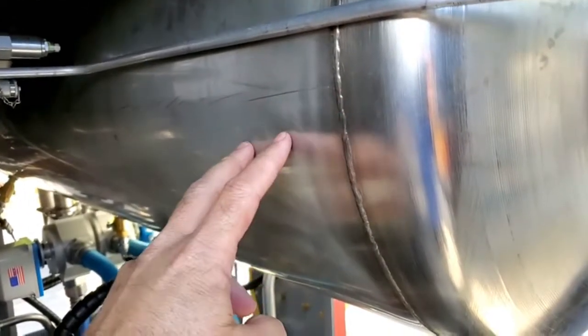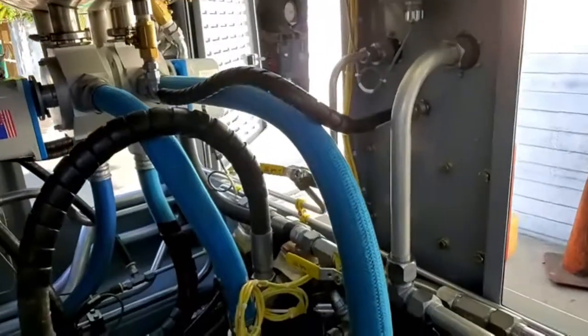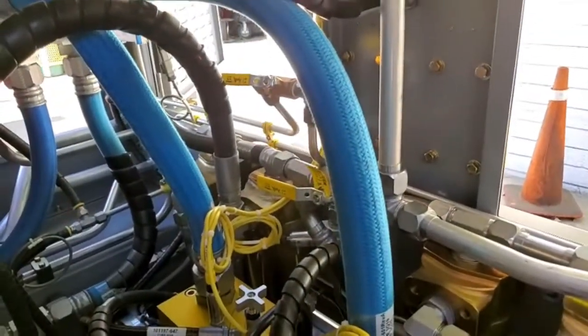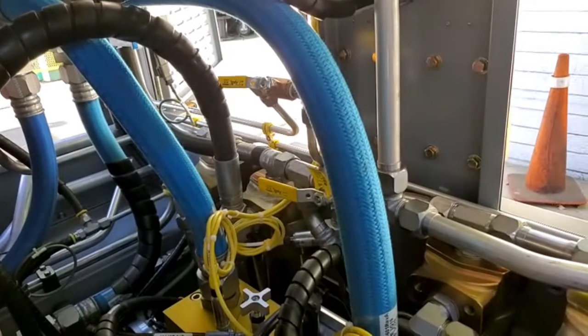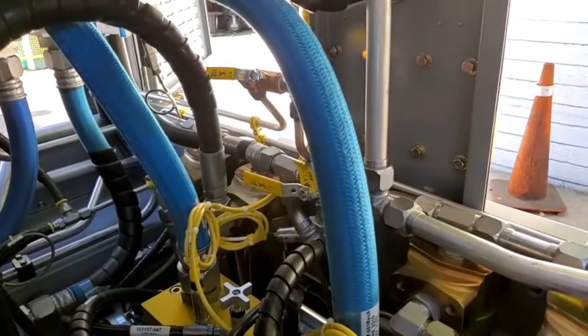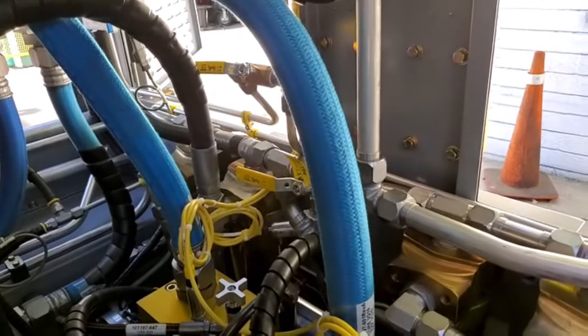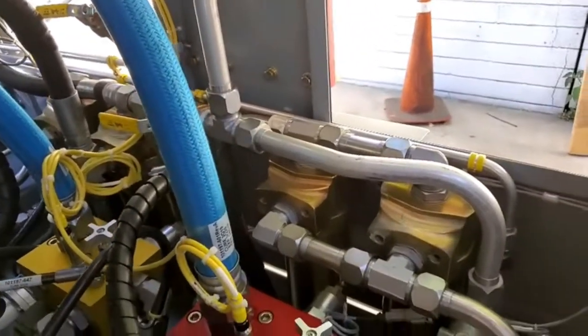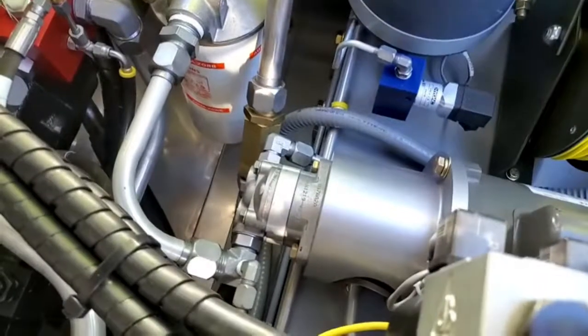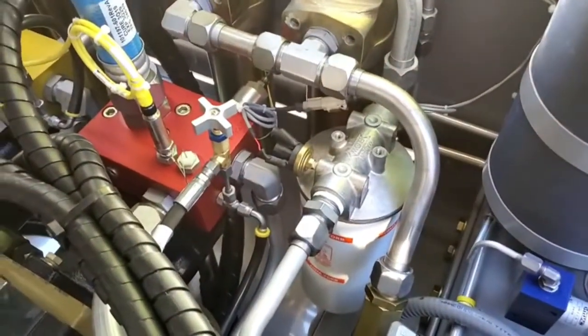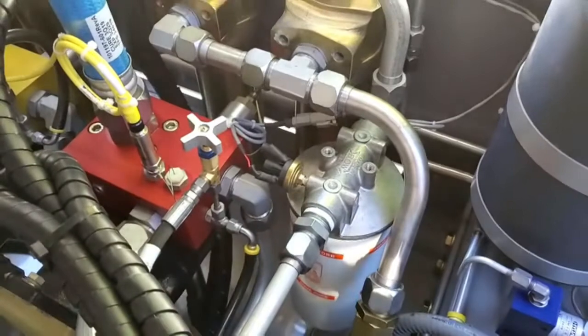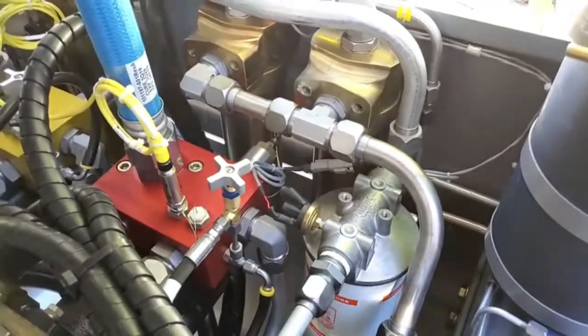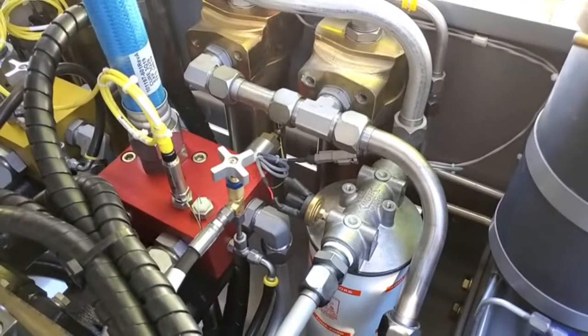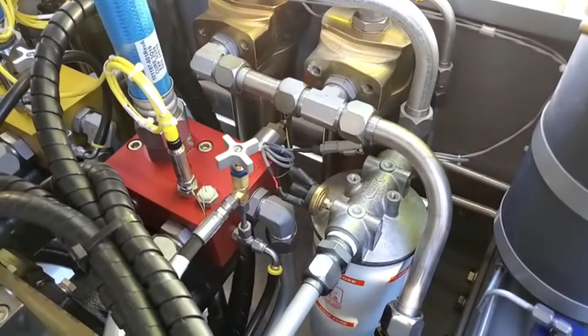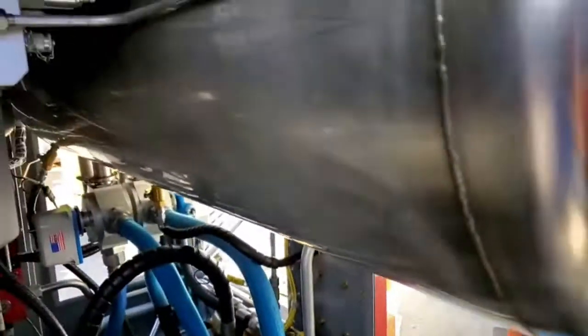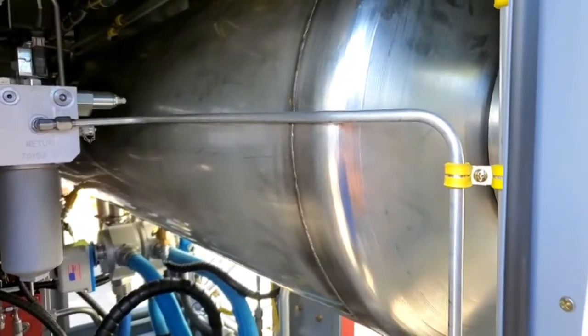So if you don't have enough fluid in this reservoir, on your supply line going to your cooling pump, remember the black line here? That cooling pump is going to draw more fluid than is available. As it draws that fluid, it creates a suction that's fighting the charge pump, located here, creating a suction which triggers this switch. So the first thing I recommend is, if you do get a moisture separator filter 1 fault, that you verify that you have the proper hydraulic fluid level in the reservoir.